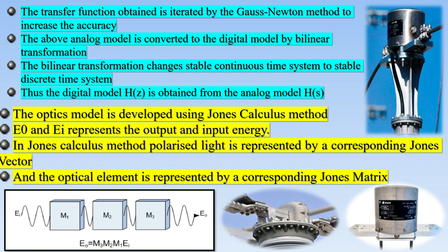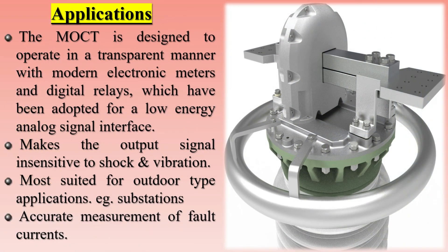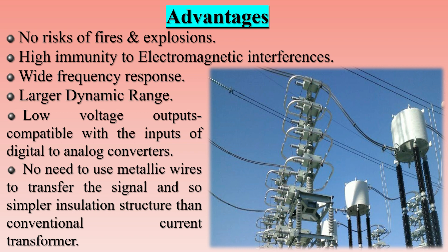Optical Current Transformers (OCTs) and conventional Current Transformers (CTs) are both used to measure current, but operate on different principles. A CT operates via electromagnetic induction — a changing current in one coil induces an EMF in another coil by varying the magnetic flux. An OCT uses light to measure current, employing an LED and photodetector to detect magnetic flux changes. Regarding output, CTs reduce high-voltage currents to a lower value for monitoring with a standard ammeter, while OCTs can have a digital output according to the IEC 61850 standard.